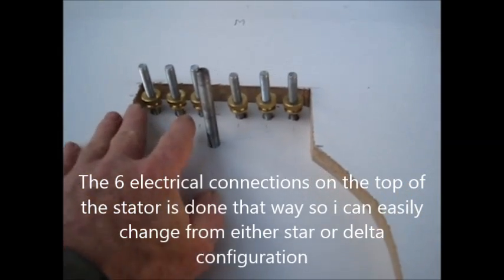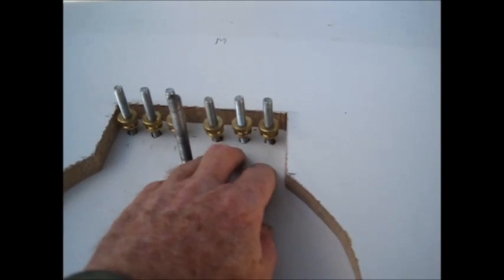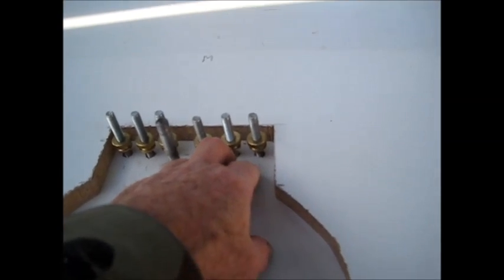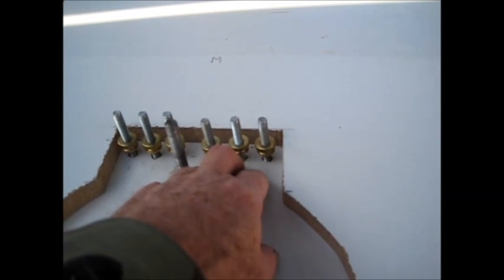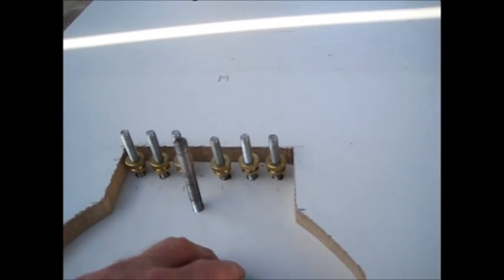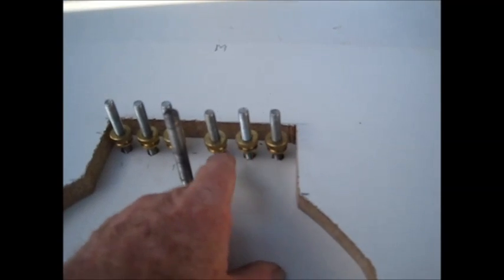So this will represent the end phase, this will be the start phase over here. Now a lot of guys I see all they have is just three connections showing on their stator mold. So whatever they've got set up in there, they're pretty much stuck with either star or delta, however they've wired up the start. With this one here, these will be exposed so I can either wire it in star or delta doing it this way.